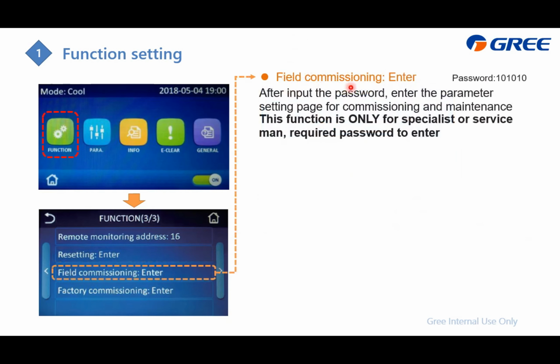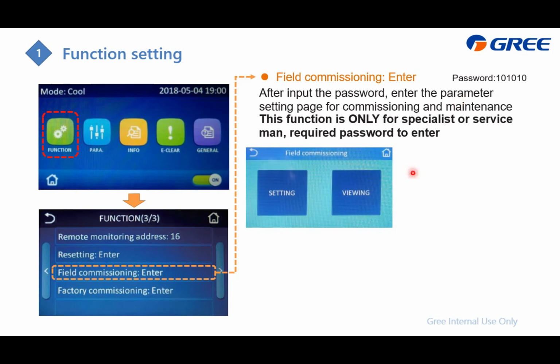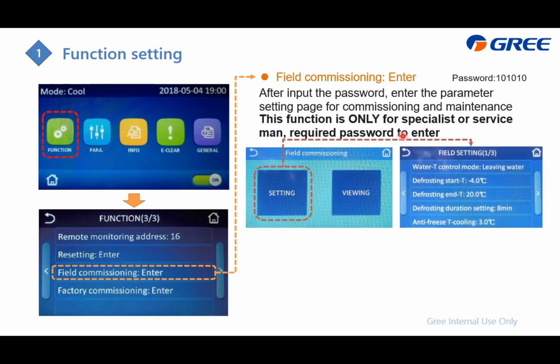Field commissioning setting. For this one, we require the password. It is here. The function is for commissioning, which means you would like to check whether the water system is okay after you install this chiller. We will go to this page, where you can set and also check the parameters. And at the setting page, which goes to this one, you can set the items.